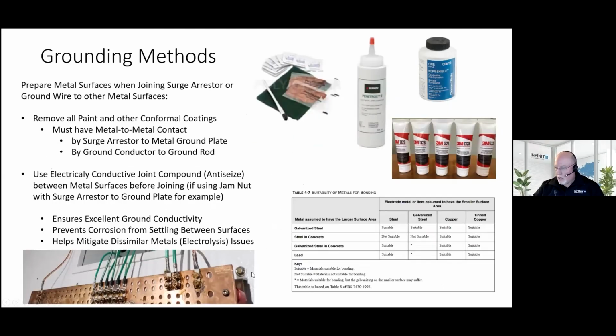Okay, so with ground bars, metal ground plates here, bus bars, or any metal surface you're attaching a ground or a surge arrestor to, like an RF coaxial surge arrestor, you want to have those ground connections or the surge arrestor having metal to metal contact with the ground bar, and you want to use a conductive joint compound between the surfaces. By doing that, you're maintaining a really good conductivity, you're preventing corrosion from settling in, and it helps with mitigating dissimilar metal or electrolysis problems, say by copper and aluminum, for example.